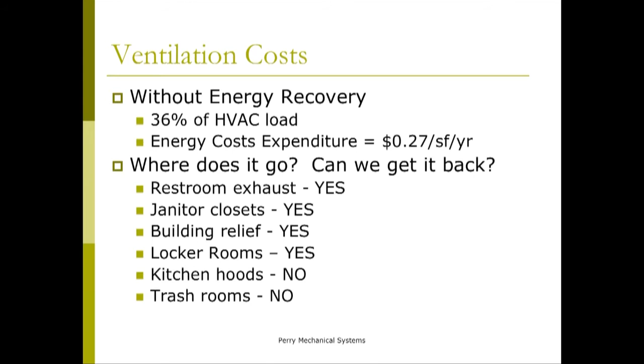And where does that go? And how do we get it back? Well, most of your ventilation, you're bringing it into the building, so you've got to get it out of the building. And a lot of it goes through your restroom exhaust, your janitor closets, locker rooms, kitchen hoods, trash rooms, and then whatever else is left over goes through your building relief. Most engineers will have either an exhaust fan or a barometric damper or something that if the building gets too pressurized, it's just going to relieve that air out of the building. And if they don't put that in, it's going to go out the door when it opens, because it's going to be positive.